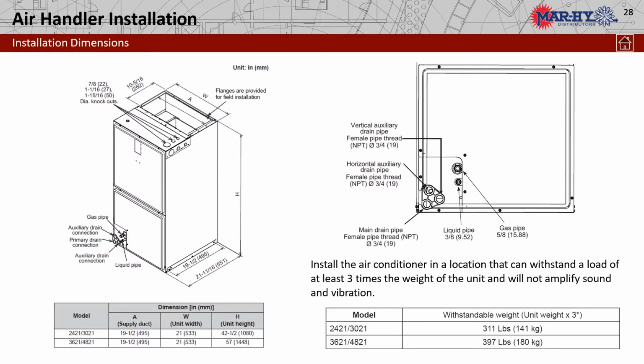As we look at it, we can see it's our conventional air handler with the electrical knockouts on top and either side, so we have good access for electrical no matter where it is. As we look at the coil cabinet itself, it is the same coil cabinet we would see on our conventional equipment. The only difference is the gas and liquid lines are flared fittings. So what does that mean? When you are tightening up those flared fittings on that coil, there's no backup on that tubing. You must use a backup wrench. Always use a backup wrench anytime you're flaring anyway. It's good practice. It keeps things together.